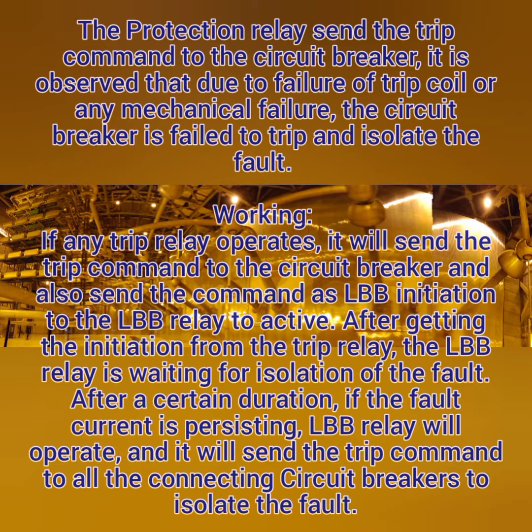The protection relay sends the trip command to your circuit breaker. It is observed that due to failure of your trip coil or any mechanical failure, the circuit breaker will fail to open or trip and isolate the fault. So the fault persists in your system in this case. In order to isolate the faulty system, we go with the local breaker backup, which enables and further isolates your faulty section from your healthy section.